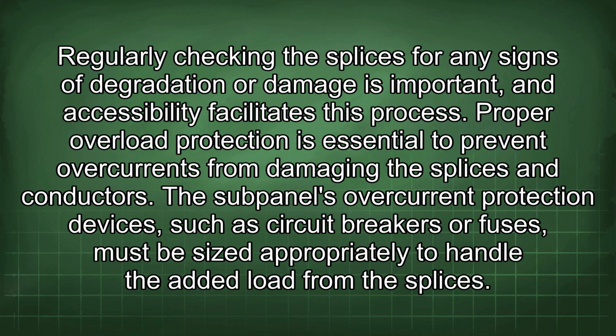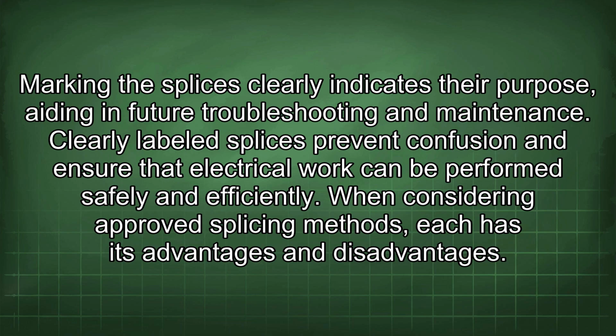Proper overload protection is essential to prevent overcurrents from damaging the splices and conductors. The subpanel's overcurrent protection devices, such as circuit breakers or fuses, must be sized appropriately to handle the added load from the splices. Marking the splices clearly indicates their purpose, aiding in future troubleshooting and maintenance. Clearly labeled splices prevent confusion and ensure that electrical work can be performed safely and efficiently.